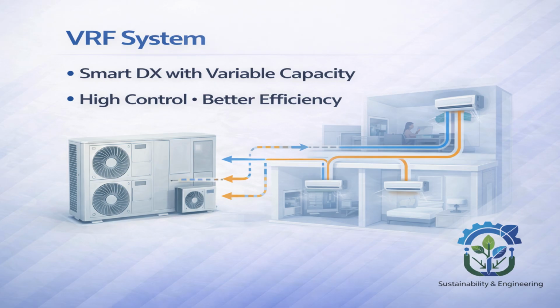In short, VRF systems offer better energy efficiency, superior zoning flexibility, and improved occupant comfort. However, VRF is not just a plug-and-play solution. It requires proper design, correct refrigerant piping, safety checks, and a well-defined control strategy. When designed correctly, VRF becomes one of the most effective HVAC systems for medium to large buildings.